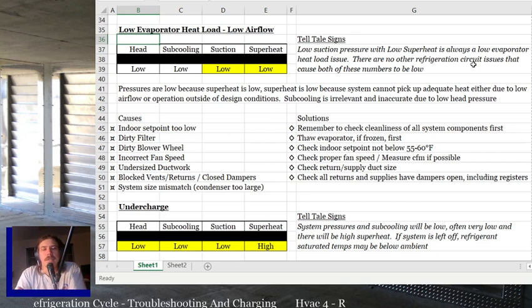So it's not all the time. There are plenty of times when it's just the filter's completely packed, or the filter's completely packed and the evaporator's dirty as hell, or whatever the case may be. It doesn't mean it doesn't happen, but I've just had it happen too many times. I've had to go back too many times on what you thought was just a dirty coil, and you didn't check the charge after that, and it turns out that it's also undercharged. So if the coil becomes a complete block of ice on the inside during AC season, check charge and low airflow. Check both, because it can be one or the other, but it's usually both.